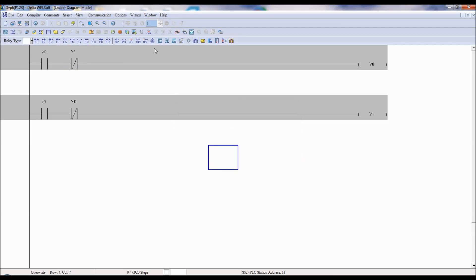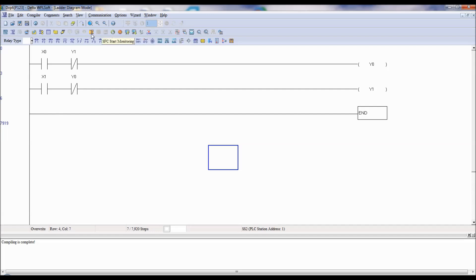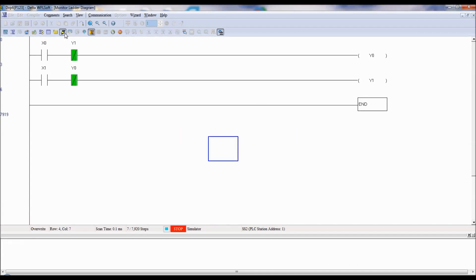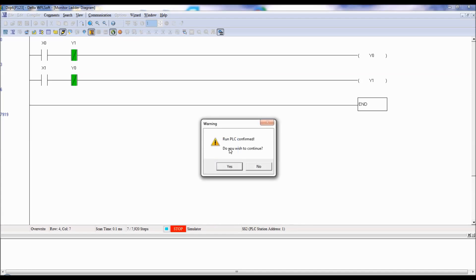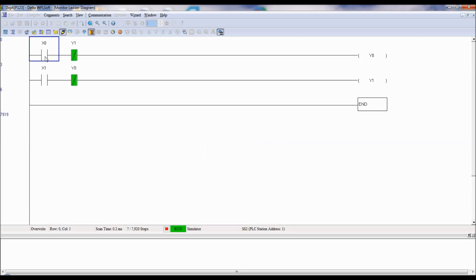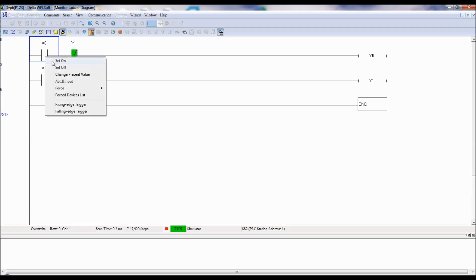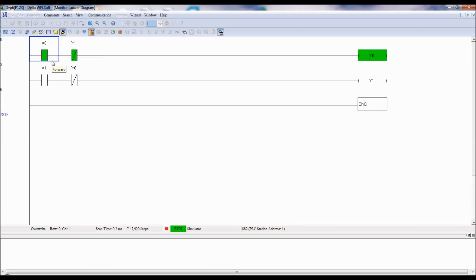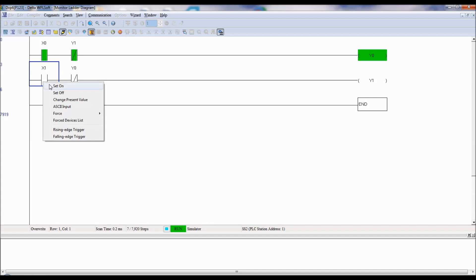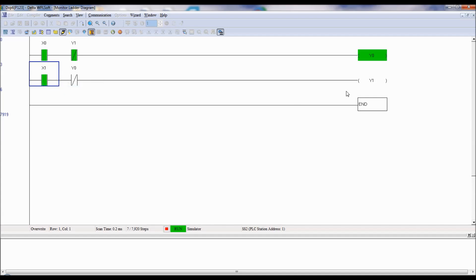So I will debug the code — there are no errors. Right now, if I don't have a PLC, I will go for simulation mode, then download the program, and then go to online mode. That is Control F4. PLC should be in run mode before checking the output — Control F11. If I press the switch for forward, the motor rotates forward because K1 relay is on. At this time, if you try to switch on the reverse button, K2 relay does not get on. This is the concept of interlocking.